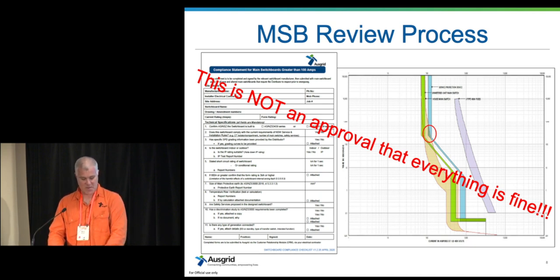Where it says report numbers, that's exactly what we need you to put in there. That doesn't mean a generic number that you as a switchboard builder or electrician have made up. It actually needs to reference the type test report that you've undertaken. It's a very quick review for our guys. If we see those report numbers and they match what we're looking at for the switchboards, they've become pretty savvy with those numbers and have a rough idea what they should look like. It's easy to say, hey guys, I'm not too sure about that. Can you send us the first page of that test report just to verify that the test was actually done?